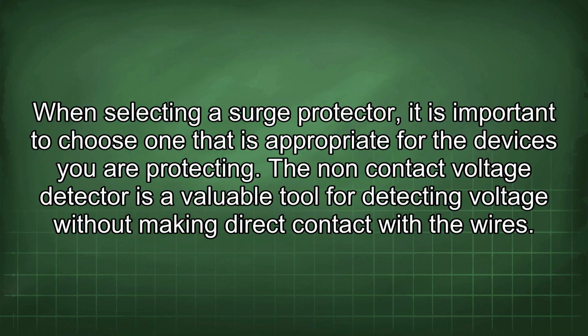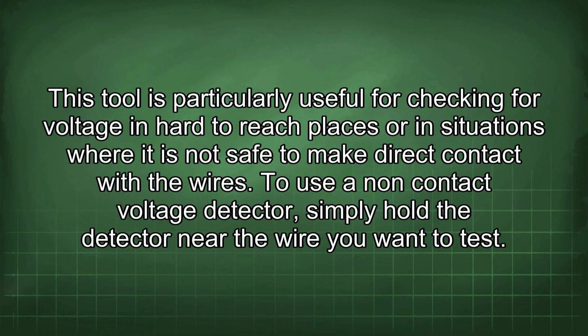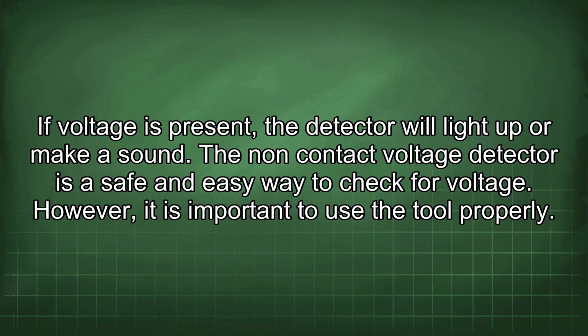The non-contact voltage detector is a valuable tool for detecting voltage without making direct contact with the wires. This tool is particularly useful for checking for voltage in hard-to-reach places or in situations where it is not safe to make direct contact with the wires. To use a non-contact voltage detector, simply hold the detector near the wire you want to test. If voltage is present, the detector will light up or make a sound. The non-contact voltage detector is a safe and easy way to check for voltage.